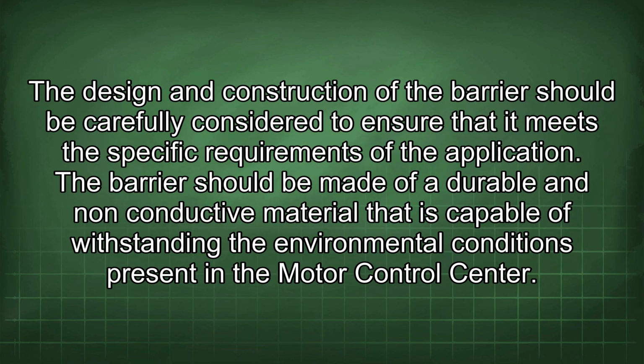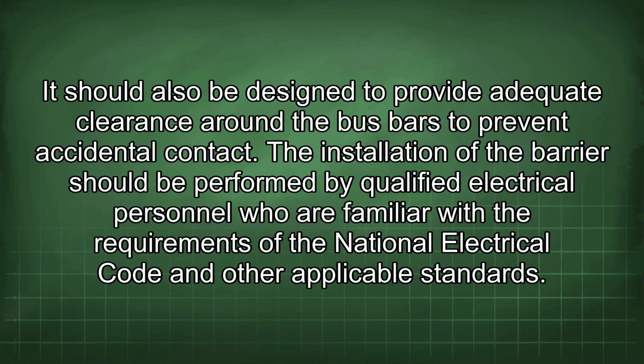The design and construction of the barrier should be carefully considered to ensure that it meets the specific requirements of the application. The barrier should be made of a durable and non-conductive material that is capable of withstanding the environmental conditions present in the motor control center. It should also be designed to provide adequate clearance around the bus bars to prevent accidental contact. The installation of the barrier should be performed by qualified electrical personnel who are familiar with the requirements of the National Electrical Code and other applicable standards.